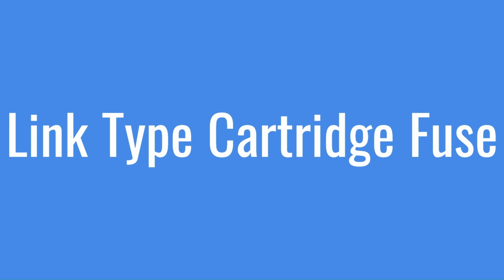Link type cartridge fuse is also called high rupturing capacity or HRC fuse. In such type of fuses, the fuse element carries the fault current for a long duration. If the fault is not cleared, then the fuse element will melt and open the circuit. The major advantage of HRC fuse is that it clears low as well as high fault current.